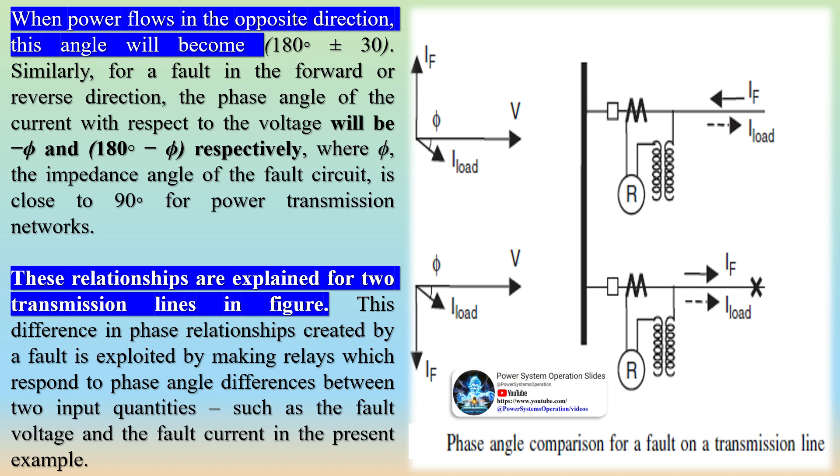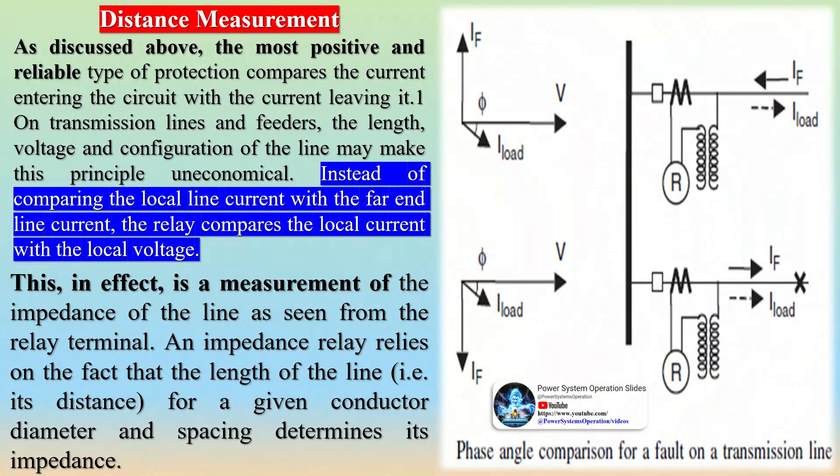When power flows in the opposite direction, this angle will become (180° ± 30°). Similarly, for a fault in the forward or reverse direction, the phase angle of the current with respect to the voltage will be -φ and (180° - φ) respectively, where φ, the impedance angle of the fault circuit, is close to 90° for power transmission networks.